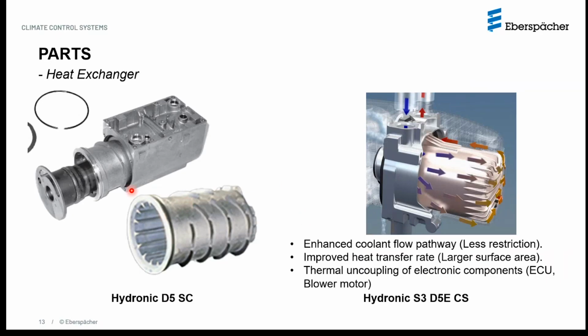We have the heat exchanger that basically allows for transfer of heat to the coolant that would be circulating around it. Of course, you have the coolant pump that does the job of drawing the coolant from the truck circuit and pushing it into the heater over the heat exchangers and then back into the truck side. The newer design allows for a much better path or flow of coolant with the minimum amount of restriction. Also, the surface area is enhanced so as to allow for a better transfer of heat.